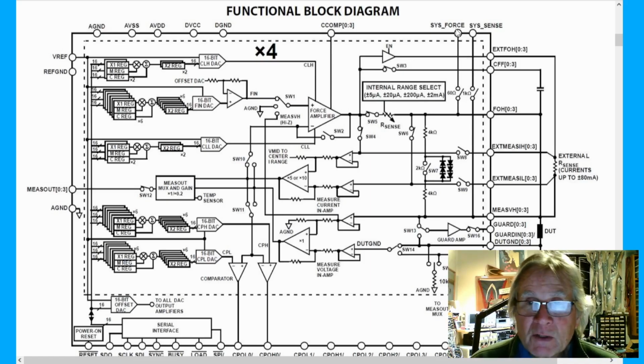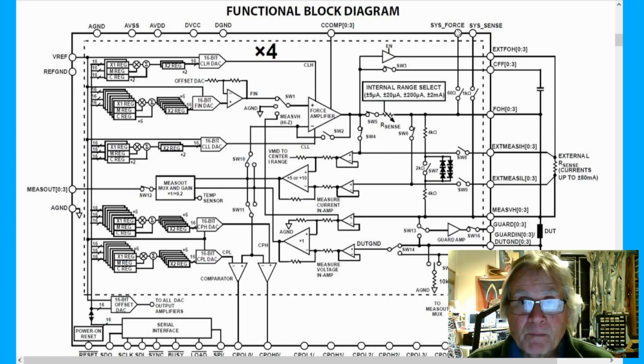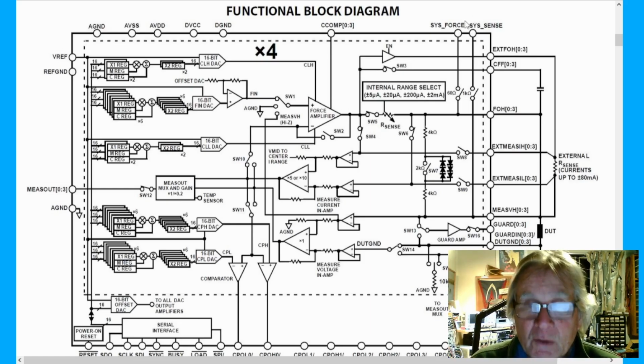My plan is to use those for calibration when I get the software at the point where it can control an external multimeter. So I'll use an external multimeter, for example, to measure the force, and then set the cal values until the outputs have the right precision.